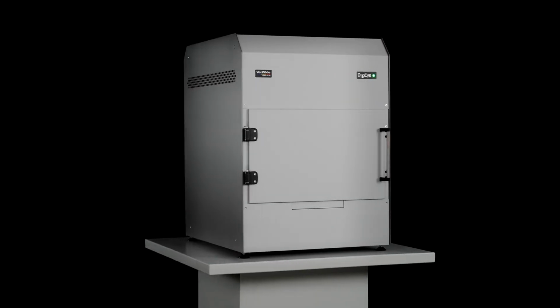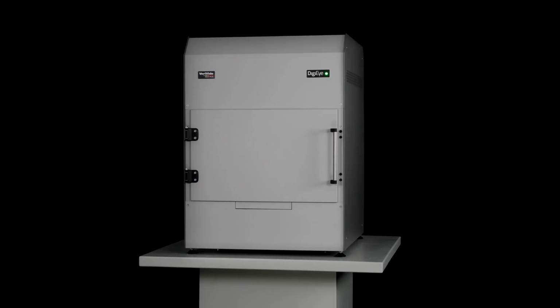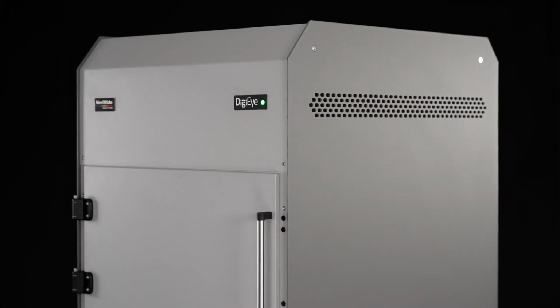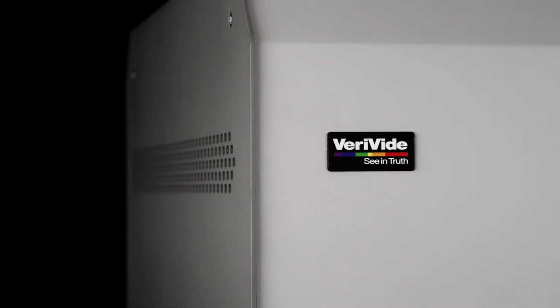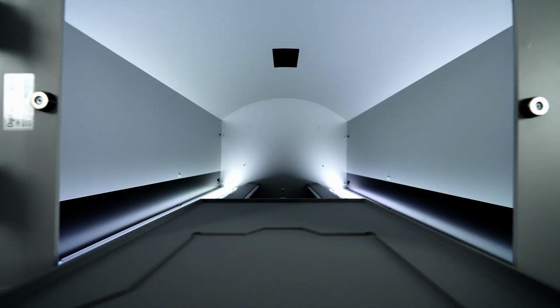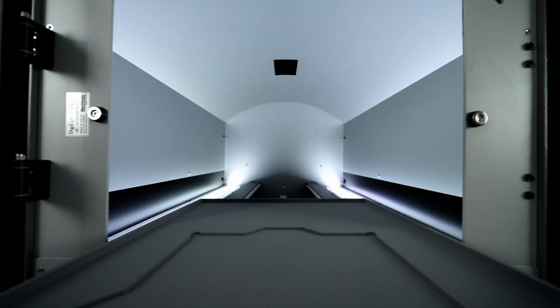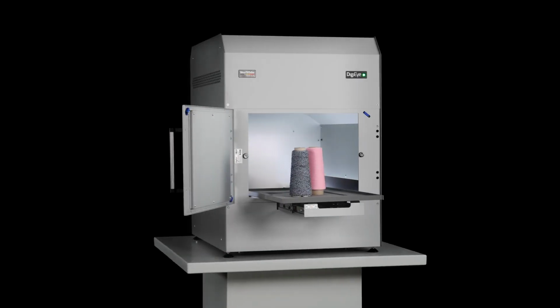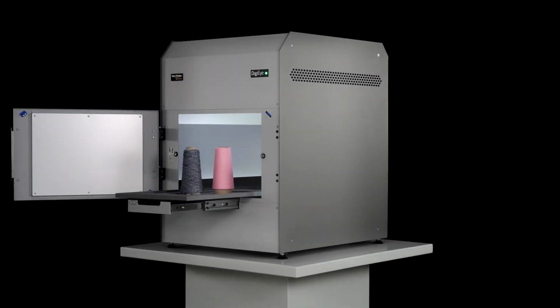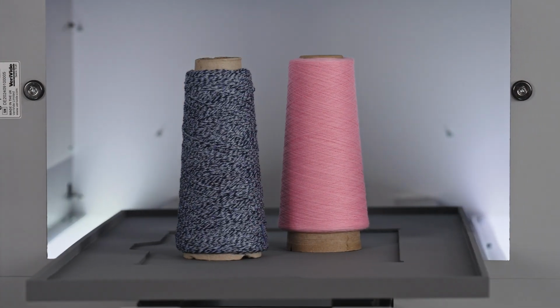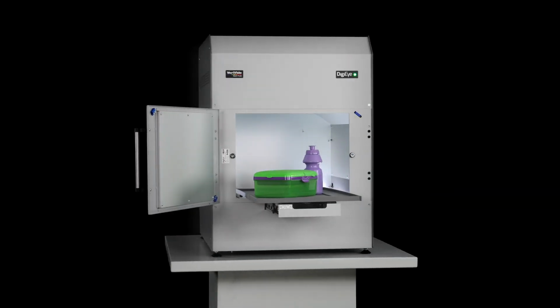Key benefits of the new DigiEye Cube are a smaller footprint for desktop use, but with a large A3 imaging area, easy access for sample positioning using the new door system, and made from a stronger metal powder-coated construction. Our state-of-the-art all-LED illuminated vision imaging system eliminates the need for regular lamp changes and features a fully tunable LED light engine. For optimum performance, a yearly calibration is required.